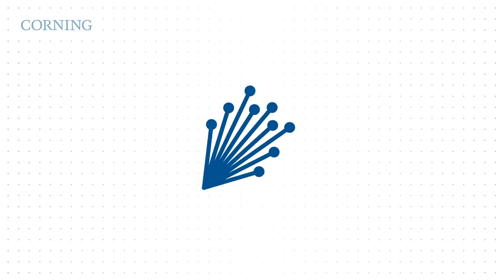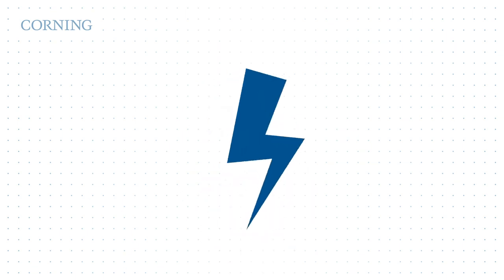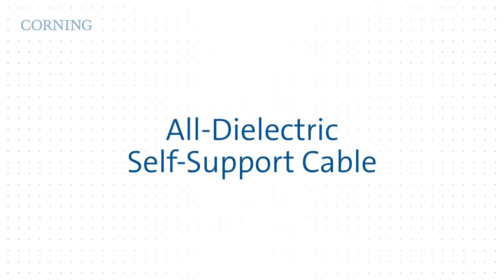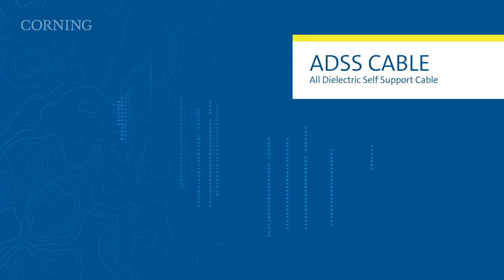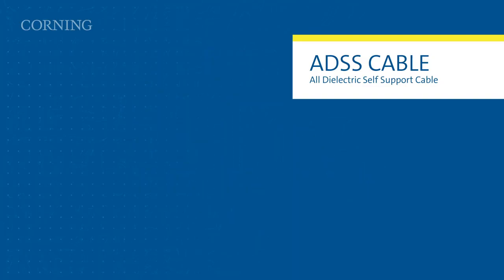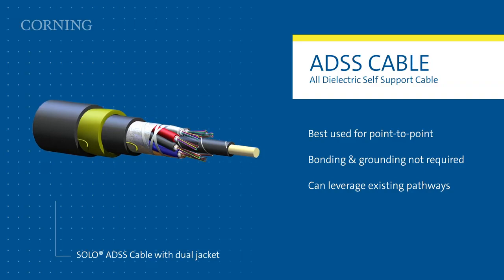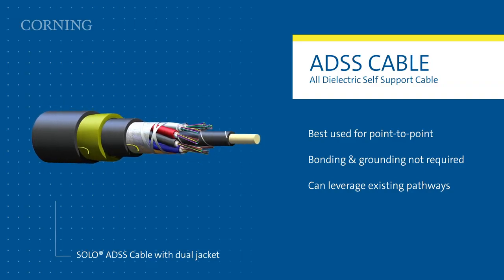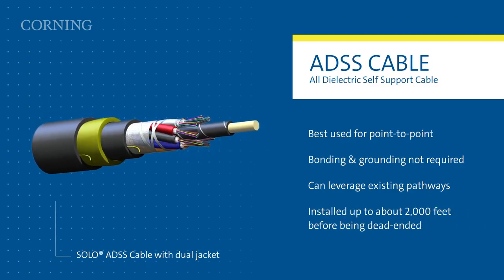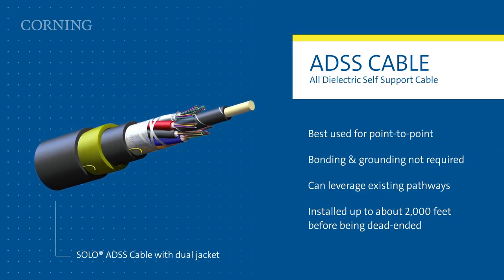The power industry has traditionally defaulted to the tried-and-true method of deploying all-dielectric self-support cable, also known as ADSS. ADSS is great for many things, especially point-to-point fiber connections with relatively infrequent need to access fiber along the route. ADSS doesn't require bonding and grounding, can leverage existing pathways on pole runs and transmission towers so new poles aren't required, and can be installed across long spans before being dead-ended.